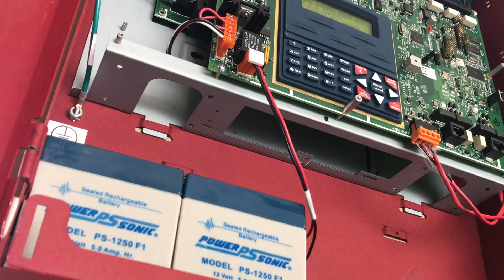How often do fire alarm systems have to be inspected? All the initiating devices and notification appliances on a fire alarm system have to be inspected at least annually, one time a year. A lot of the times we go to places only once a year to inspect their fire alarm systems. However, there are other places we go, usually larger places like hospitals, where we can go up to about 4 times a year for their inspections.